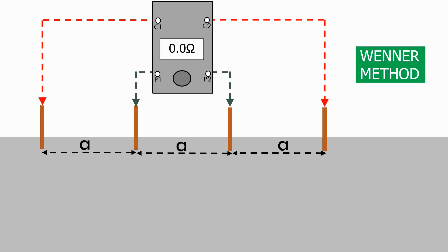To perform this test we drive four equally spaced rods into the ground. I connect a testing wire to each of the rods and connect them to a meter to measure the resistance.